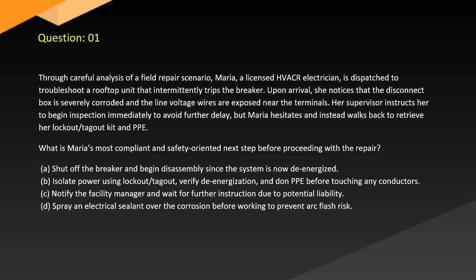Question 1. A careful analysis of a field repair scenario. Maria, a licensed HVACR electrician, is dispatched to troubleshoot a rooftop unit that intermittently trips the breaker. Upon arrival, she notices that the disconnect box is severely corroded and the line voltage wires are exposed near the terminals. Her supervisor instructs her to begin inspection immediately to avoid further delay, but Maria hesitates and instead walks back to retrieve her lockout kit and PPE.